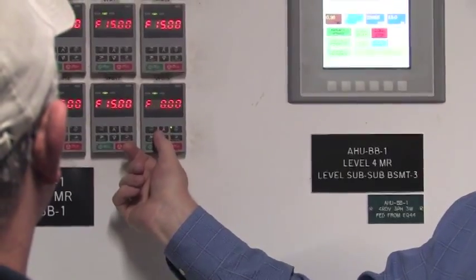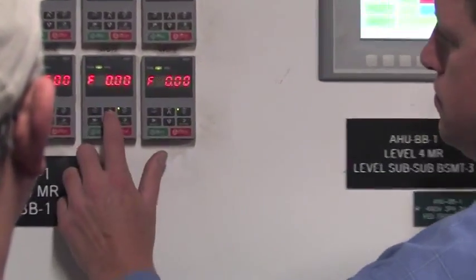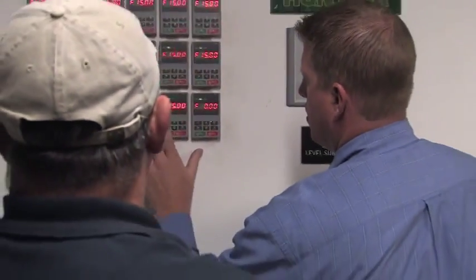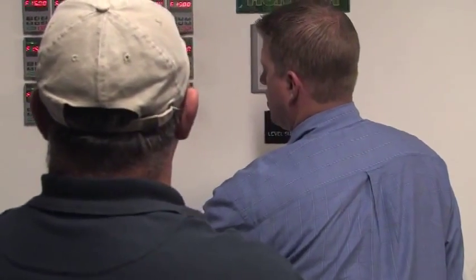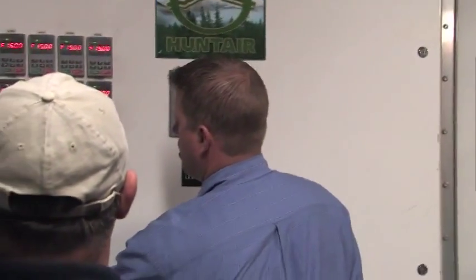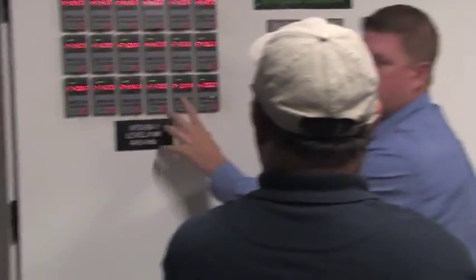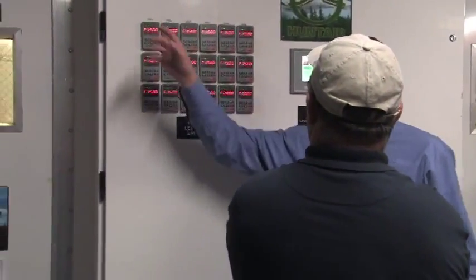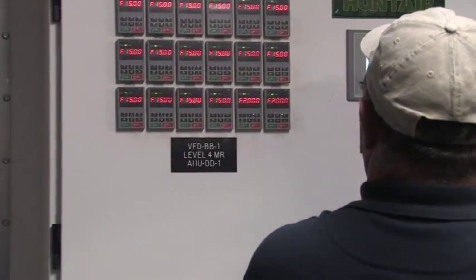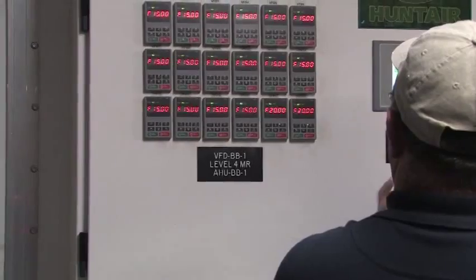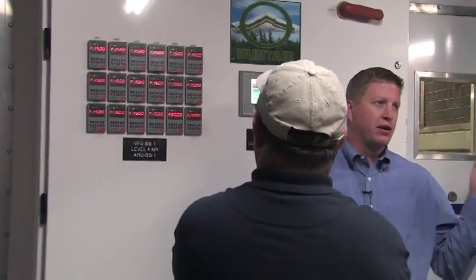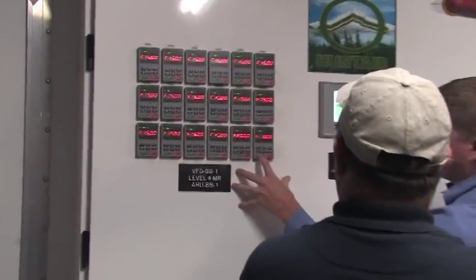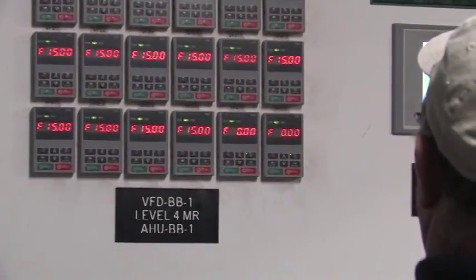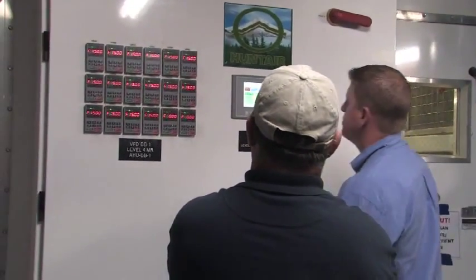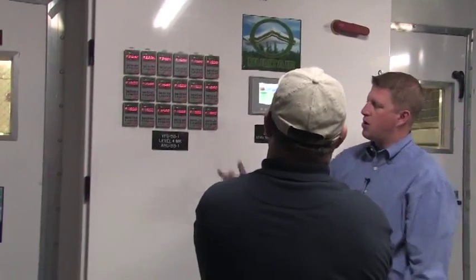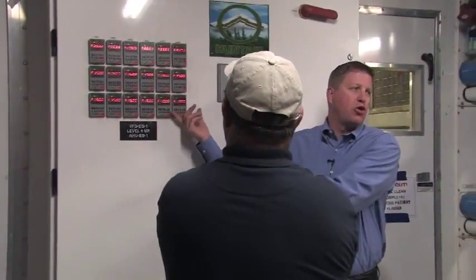Set my hertz. Let's set it to 20. Right, and I would do that to all of them. And once they were all set, they'd all have to be at the same hertz, because you don't want an imbalance. You don't want some doing 20, some doing 60. You set them all to the same hertz, and then I'd simply go through and hit run, run. And you'll see those two fans come on. You can see it's registering a flow right now. So I'm running two fans right now at 20 hertz in hand from the drive level.